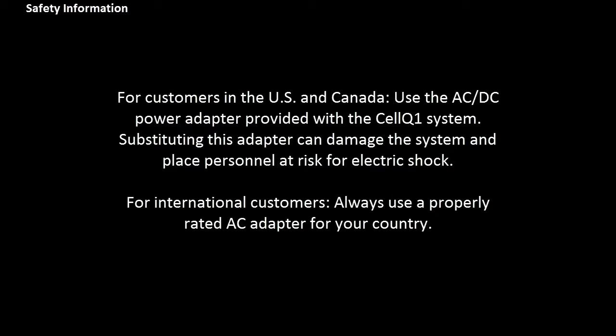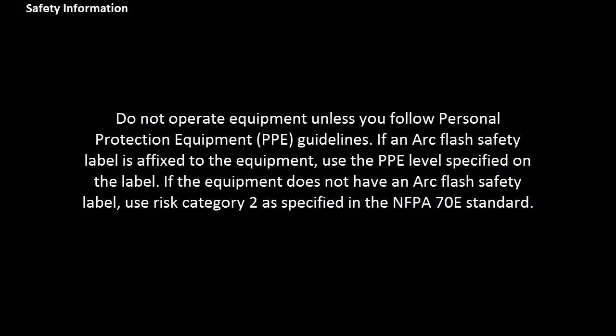For customers in the US and Canada, use the AC/DC power adapter provided with the CellQ1 system. Substituting this adapter can damage the system and place personnel at risk for electric shock. For international customers, always use a properly rated AC adapter for your country. Do not operate equipment unless you follow personal protection equipment guidelines. If an arc flash safety label is affixed to the equipment, use the PPE level specified on the label.